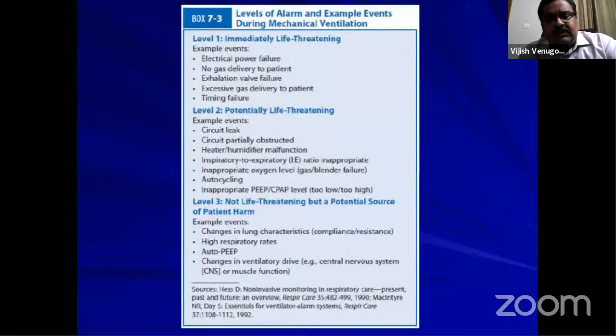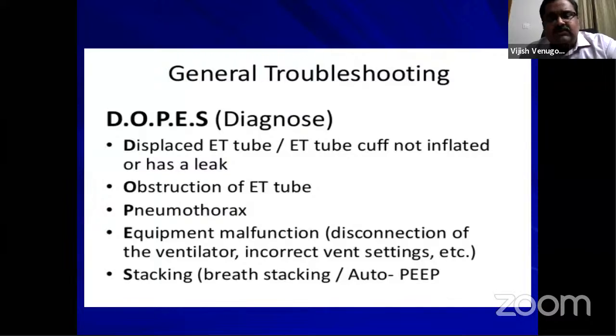Similarly, we get alarms, different levels of alarms, level 1, level 2, level 3 alarms are there. So it is very important that you don't just go on silencing the alarm, but see what the alarm is and manage. So, 2 slides on general troubleshooting. You can remember it as DOPES, that is to diagnose the trouble. DOPES stands for displaced ET tube or ET cuff which is not inflated or has a leak. O is for obstruction of the ET tube. P is for pneumothorax. E is for equipment malfunction, and S is for stacking or dyssynchrony of the patient. That is development of auto-PEEP or breath stacking.